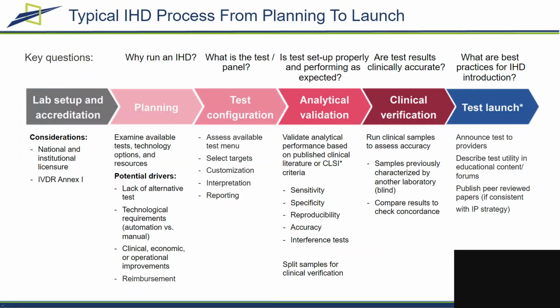For the analytical validation, you will do a classic validation following probably the CLSI guidelines, which would cover how you would determine an adequate sensitivity, specificity, reproducibility, accuracy, and also prove that you don't have interference from known components that might be in the same patient sample. And you would split samples for clinical verification.